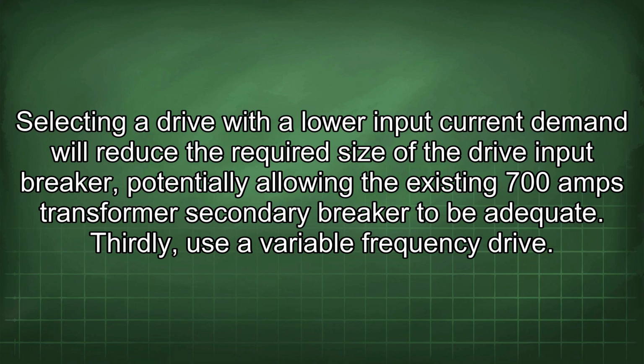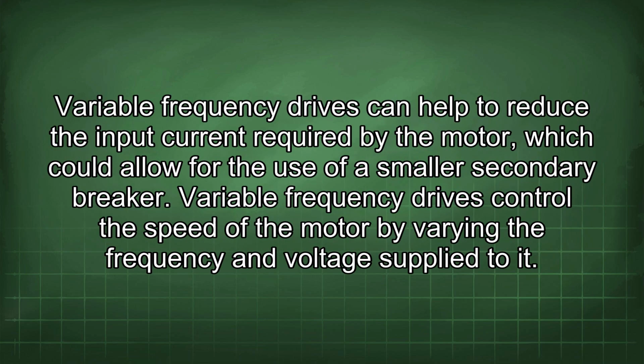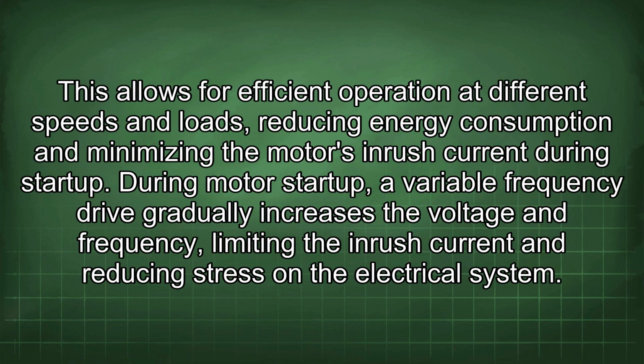Thirdly, use a variable frequency drive. Variable frequency drives can help to reduce the input current required by the motor, which could allow for the use of a smaller secondary breaker. Variable frequency drives control the speed of the motor by varying the frequency and voltage supplied to it. This allows for efficient operation at different speeds and loads, reducing energy consumption and minimizing the motor's inrush current during startup. During motor startup, a variable frequency drive gradually increases the voltage and frequency, limiting the inrush current and reducing stress in the electrical system.